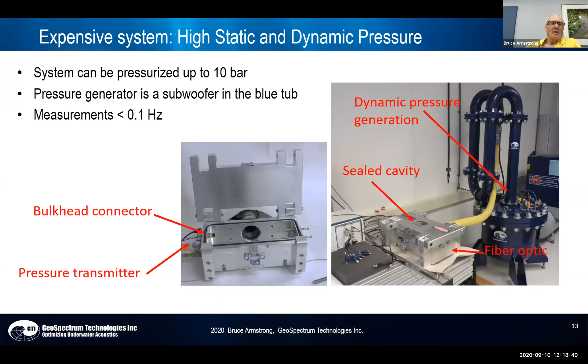The sealed container in this case is machined out of metal. It has a bulkhead connector to get signals out. It's got a pressure transmitter fastened into the side as a reference transmitter, reference hydrophone. And it's got that big blue tub with a very large subwoofer in it to generate pressure. And you can see a folded pipe in the picture. That is just a means to create a resonance to amplify the amount of pressure produced by the speaker. You don't need that.